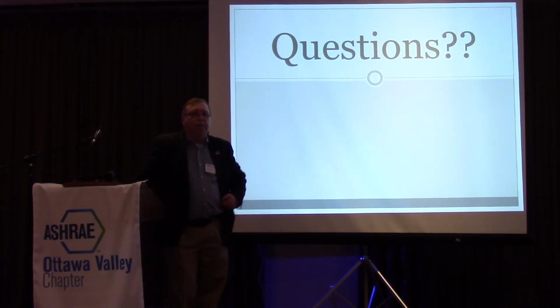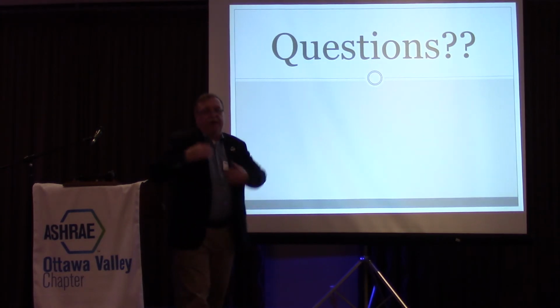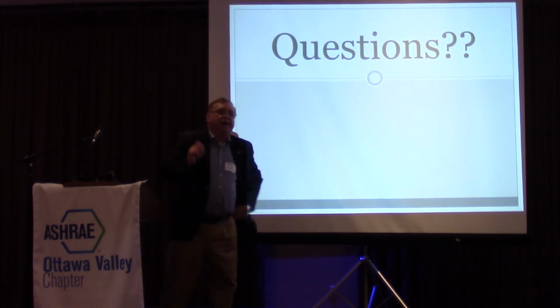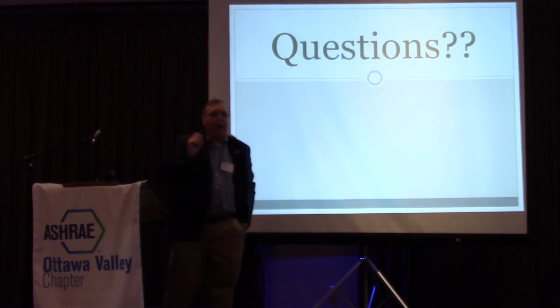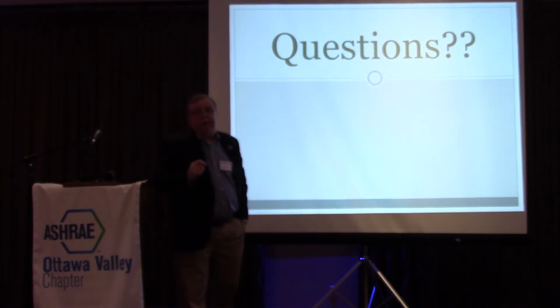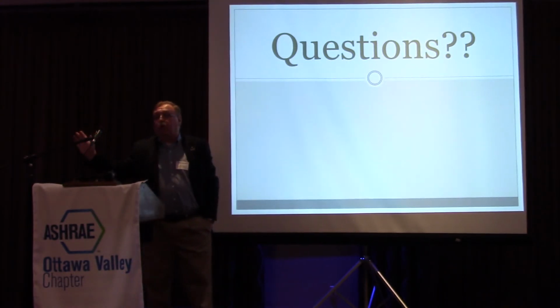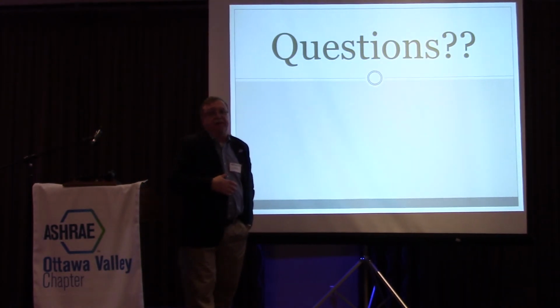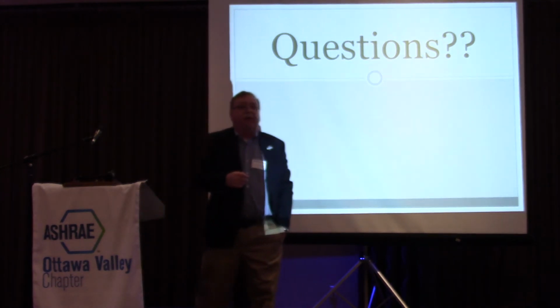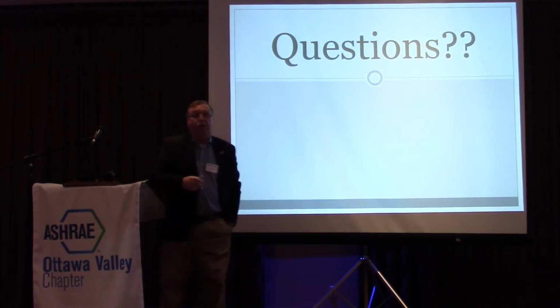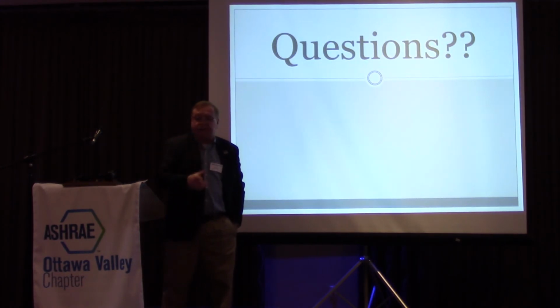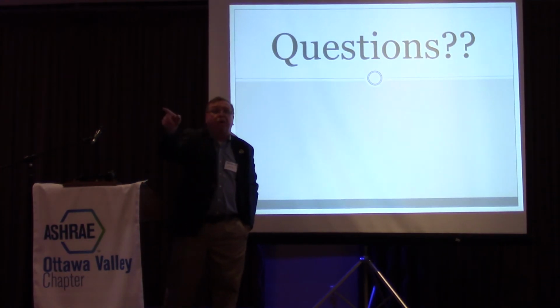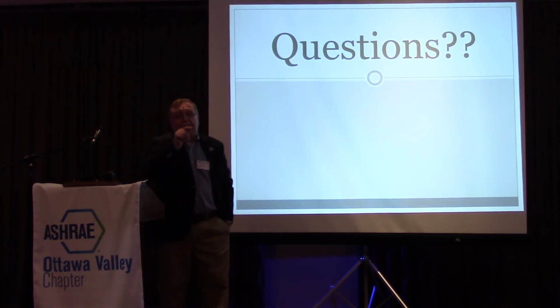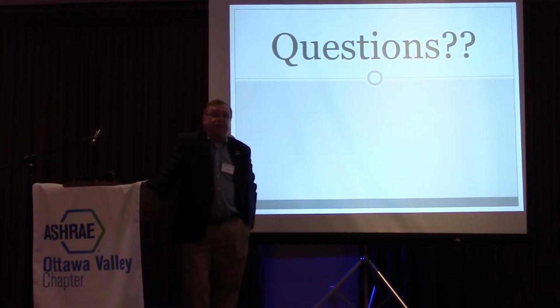So are you seeing that everyone in California is using certified seismic equipment? In the US code, it's listed as the AHJ has the right to ask you for that documentation. In California, they just do it all the time. Other parts of the United States, it's hit or miss whether the local inspector knows what to ask for. But he can legally, in the United States, say, oh, that chiller you're planning on putting in my hospital in Memphis, I want to see documentation. And if he doesn't have it, he's out.